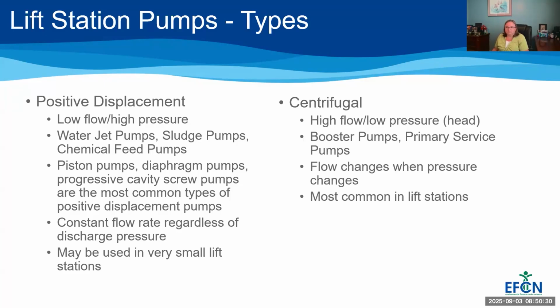So sometimes they're used in lift stations and smaller lift stations, but they're not nearly as common as centrifugal. But sometimes you will see a screw pump in a lift station. But your centrifugal pumps are where you have typically more of a high flow, a low pressure. These are your booster pumps, typically your primary service pumps. And your flow changes when the pressure changes. So you can get different flow rates depending on the pressure that you're pumping against. And again, these are the most common type in lift stations.